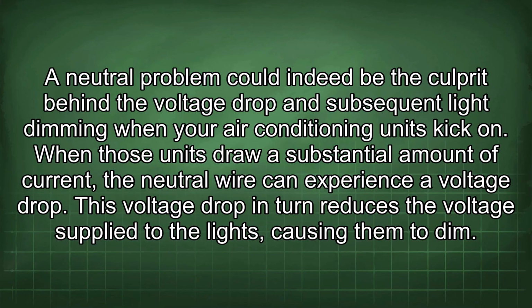A neutral problem could indeed be the culprit behind the voltage drop and subsequent light dimming when your air conditioning units kick on. When those units draw a substantial amount of current, the neutral wire can experience a voltage drop. This voltage drop in turn reduces the voltage supplied to the lights, causing them to dim.